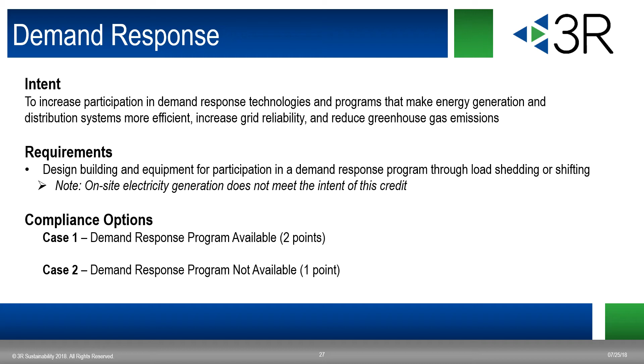In order to document this one, you'll need to provide evidence of the ability to shed 10% of your peak demand, confirmation that your system is capable of receiving and acting on an external signal, an action plan for meeting the reduction requirement during an event, and proof that you've included demand response in your commissioning system's testing plan. The only difference between using the 2 options is that under option 1, you must also provide evidence that your project has enrolled in an active program.